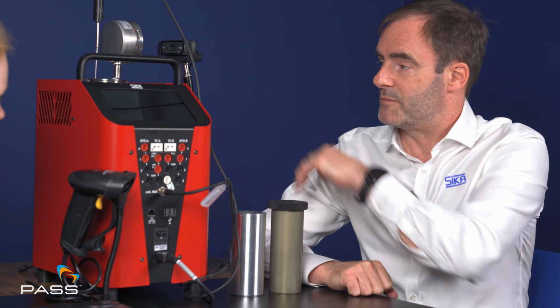As you've explained, the Sika Premium Temperature Calibrators, 4 functions, make it extremely versatile. However, this versatility is somewhat hampered if it can only calibrate one device at a time. So what has Sika done to ensure that their premium temperature calibrators are not limited in this way? We use the AirShield dry block unit, where we can put up to 48 different sensors within the unit.